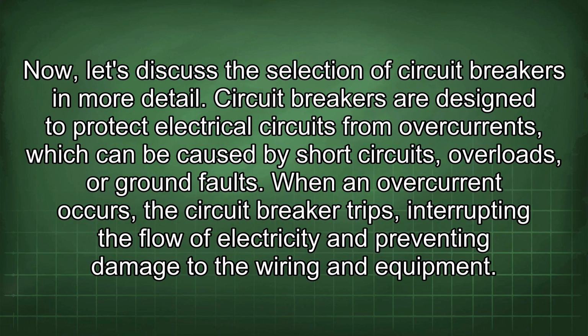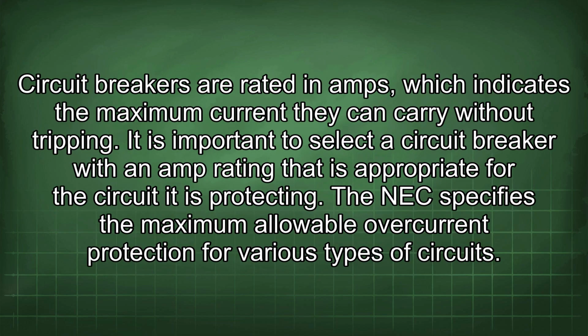Now let's discuss the selection of circuit breakers in more detail. Circuit breakers are designed to protect electrical circuits from overcurrents, which can be caused by short circuits, overloads, or ground faults. When an overcurrent occurs, the circuit breaker trips, interrupting the flow of electricity and preventing damage to the wiring and equipment. Circuit breakers are rated in amps, which indicates the maximum current they can carry without tripping.